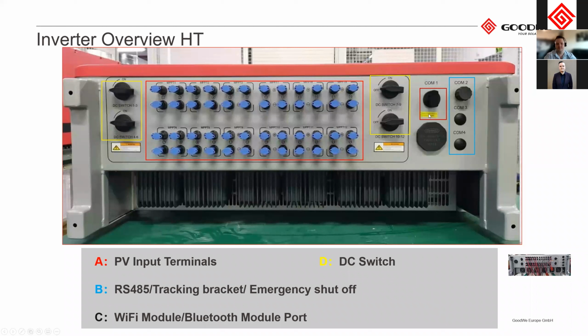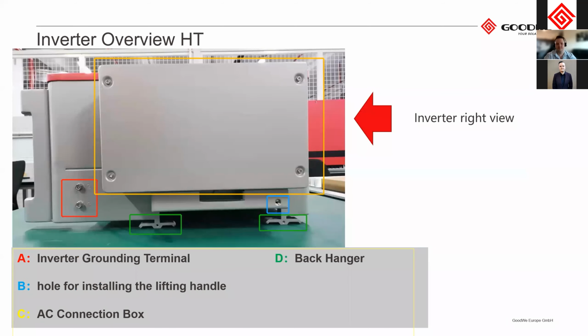Then we have our communications port here and our alternative communications port as well. So COM1 is for the Wi-Fi and Bluetooth. COM2 is going to be for your RS485 bus. This is the right-hand side view of the HT inverter. So on the side, we have our AC terminal box, as well as 2 grounding insulation points, the back bracket mounting points, and the lifter, so holes for you to lift the devices.